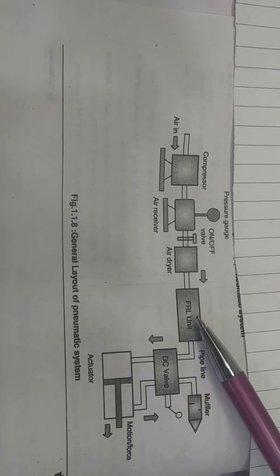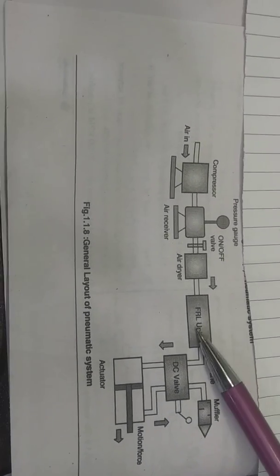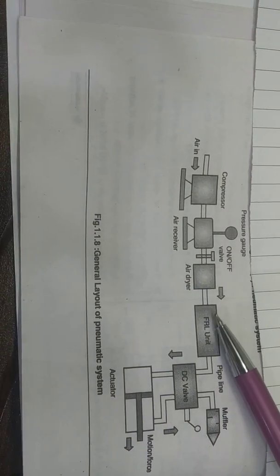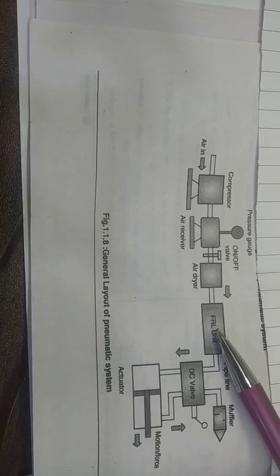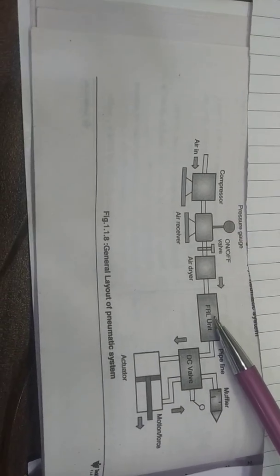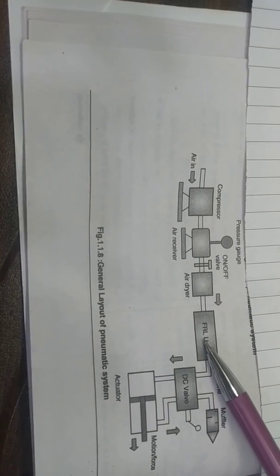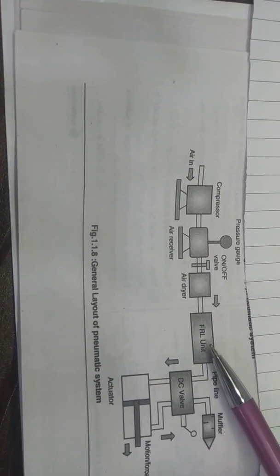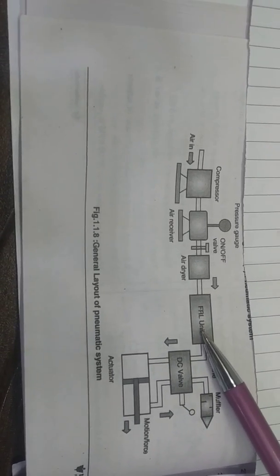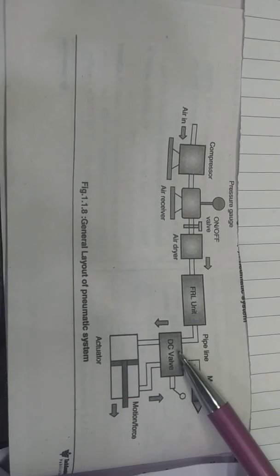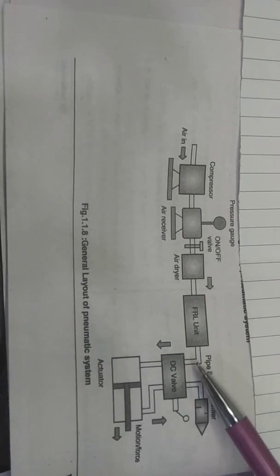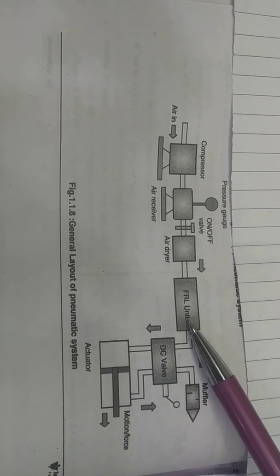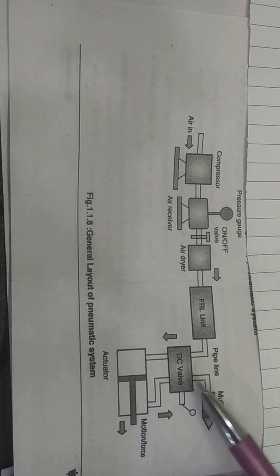The next component is the FRL unit — F stands for filter, R means regulator, and L means lubrication. Whatever air comes from the dryer gets filtered through the filter. The regulator has a knob through which we can regulate the pressure of the air. For lubrication, some oil particles are added into the compressed air. If dry air is supplied to the components, it will cause corrosion of the moving parts, so lubrication is provided to avoid this.